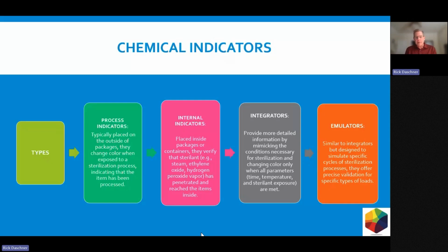Now, integrators are a chemical indicator. They look just like all the other indicators in terms of type 4s and type 5s and 6s. We'll talk about that. But they provide more detailed information by mimicking the conditions necessary for sterilization, changing color when all parameters are met, and that is time, temperature, and exposure. And then emulators, or our type 6, are almost more stringent than a type 5, which was the integrator. It's similar to integrators, but it is designed to simulate specific cycles of the sterilization process, offering precise validation with specific types of loads. And that one, used in conjunction with a biological indicator, can be really effective.